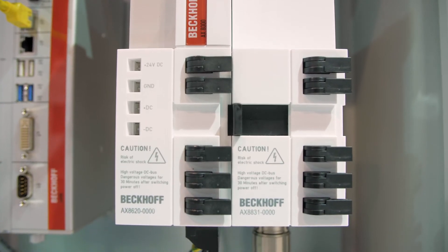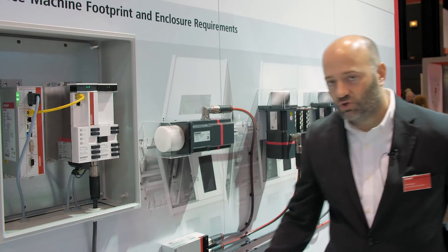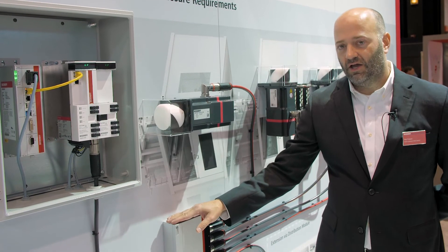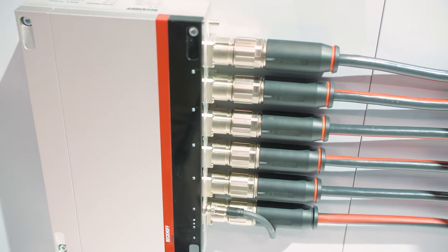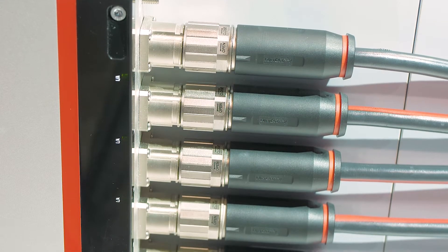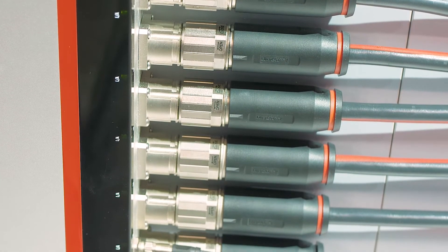It minimizes the cabling going out from the cabinet into a distribution module, the AMP8805. This AMP8805 will support up to four to five motors depending on your application. With the AMP 8000 we've introduced a distribution module that is machine mountable with an IP65 rating.